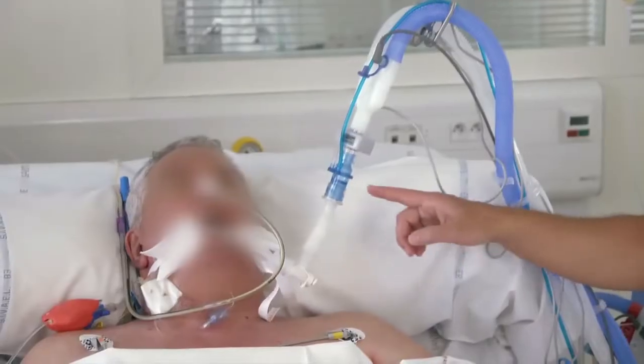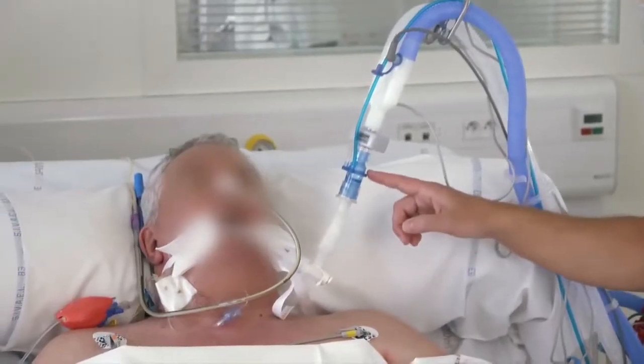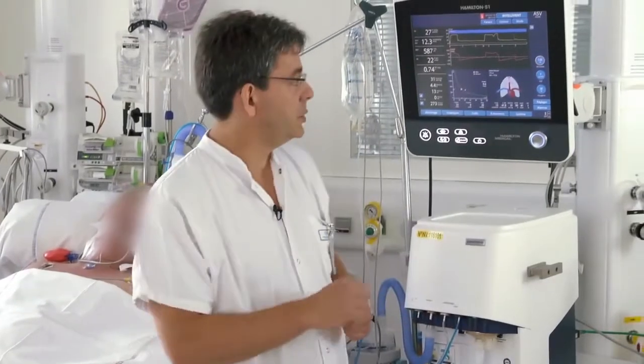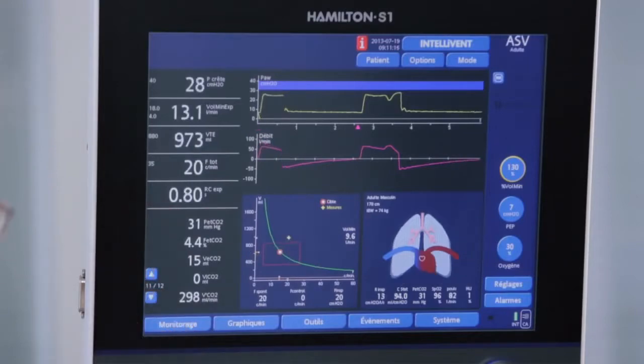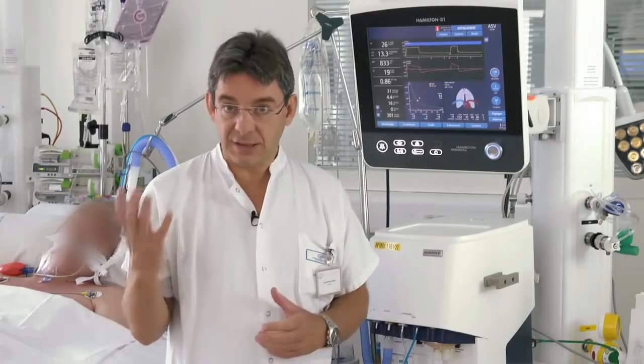The ventilator measures the respiratory mechanics using a proximal flow sensor — namely, it measures the expiratory time constant. The expiratory time constant is a mix of the static compliance and the respiratory resistances.